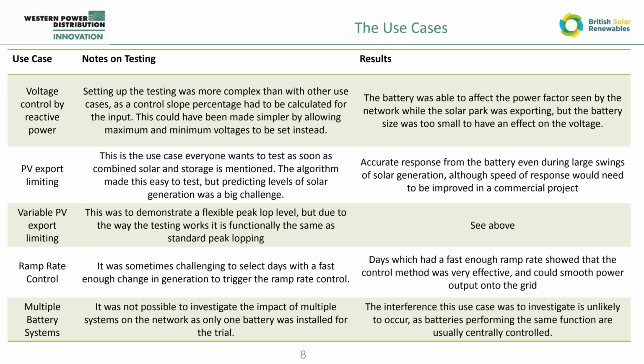PV export limiting was the case that everyone immediately thinks of when you combine a solar park with a battery. So you import power during the middle of the day, potentially when there's a grid constraint, and so you allow oversized parks on smaller grid connections, and then they export in the evening where the solar park is no longer using its export allowance.